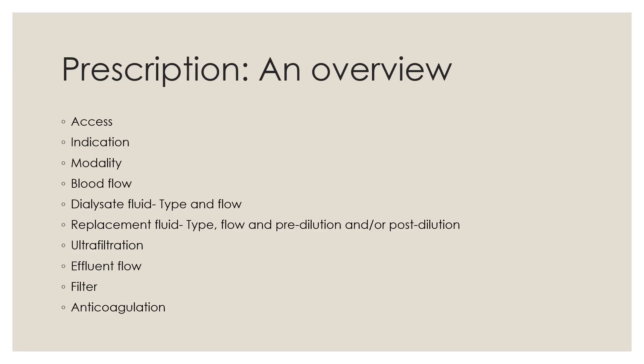It also includes replacement fluid rate if any, type and whether pre-dilution, post-dilution or both, net ultrafiltration rate, filter type, and anticoagulation.